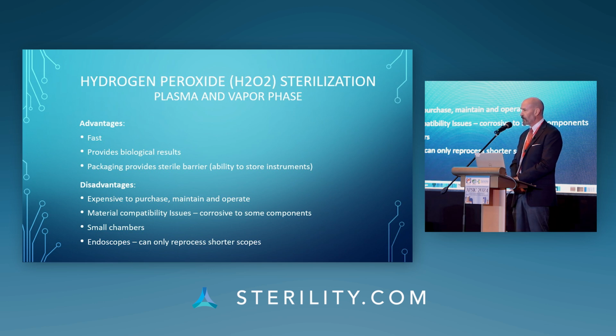The disadvantages of hydrogen peroxide are significant also. There are a great many materials that you cannot put into a hydrogen peroxide sterilizer. These systems tend to have small chambers, which means that you're running them throughout the day, which increases your consumable costs. But for today's conversation, I'd like to focus on one of the limitations of hydrogen peroxide that is not widely discussed, and that is that hydrogen peroxide systems can only process shorter scopes.